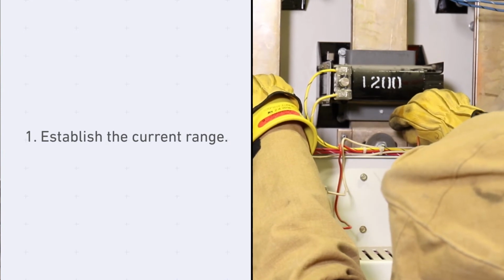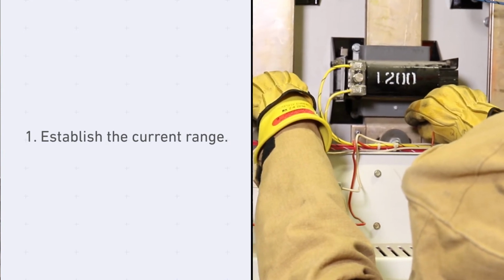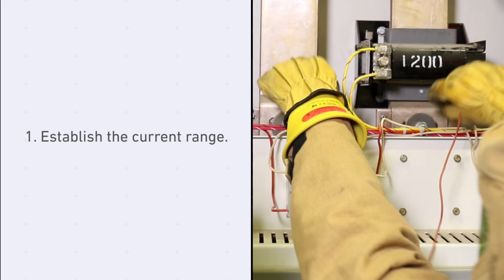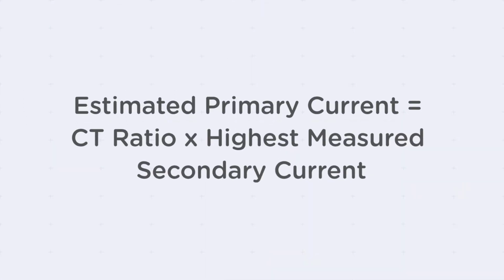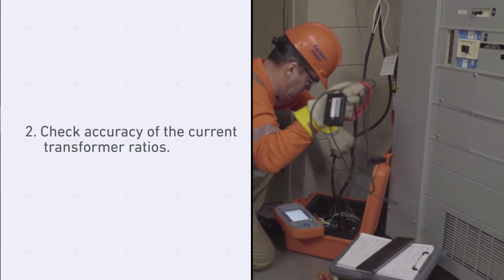This can be done by using the primary rating of the current transformers, but a common practice is to take the highest secondary current being measured by the analyzer, then multiply it by the ratio of the CTs to determine existing load at the time of testing. 2.